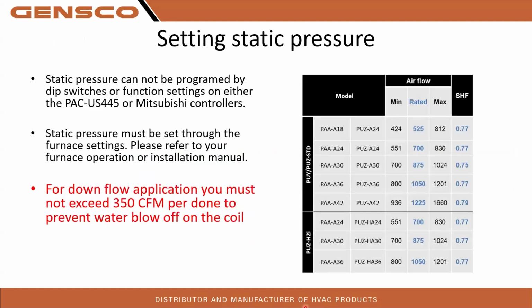Static pressure, again, cannot be programmed by dip switches or function settings on either the 445 or Mitsubishi controllers. So it has to be done through your furnace. Static pressure must be set on the furnace settings. Refer to your furnace operation or install manual for that. So right here is a chart for different coils and the rated airflow of what you want to set your airflow to. So make sure you pull out your install manual. Hopefully you still have it, or service manual, or try to find it online. That way you guys can see what to set your airflow to.